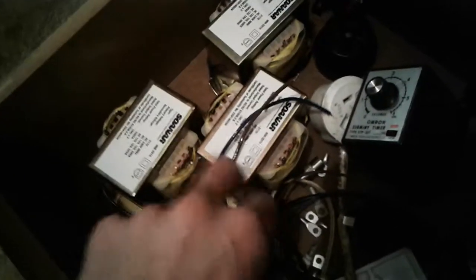2 secondary coils, 50 volt amp each. These require 70 volt amp to fully close. So if I put 2 secondaries in parallel, I'll get 100 volt amps, which would nicely get that contactor going.